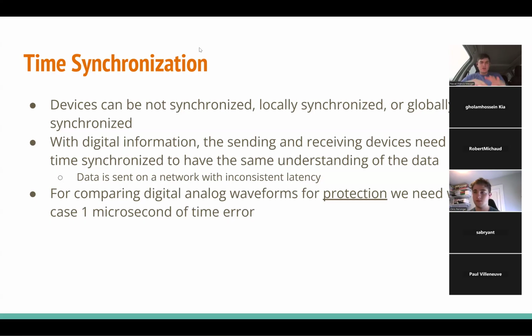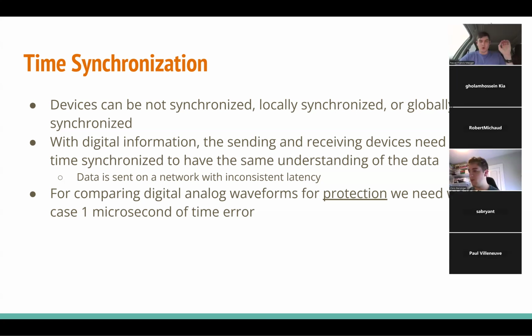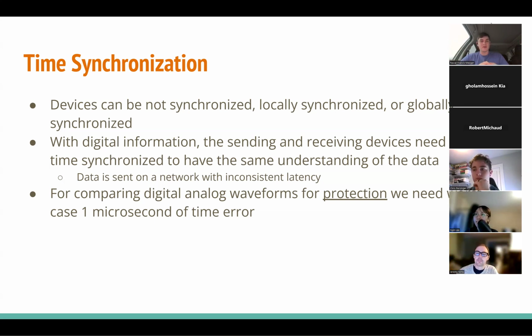I just wanted to reiterate a couple things from last week, because I know it was pretty quick, but this is a really important topic: time synchronization, which occurs in every substation, whether conventional or digital. I want to make sure this is a concept you understand. The reason we have to do this is because every device in a substation has the capability of keeping its own time. So you might think we should just set them all to the same time and then everything's great. Why do we need continuous time synchronization? The reason is because clocks drift.